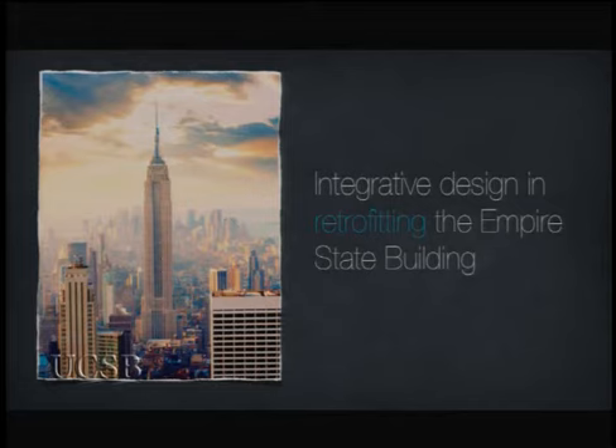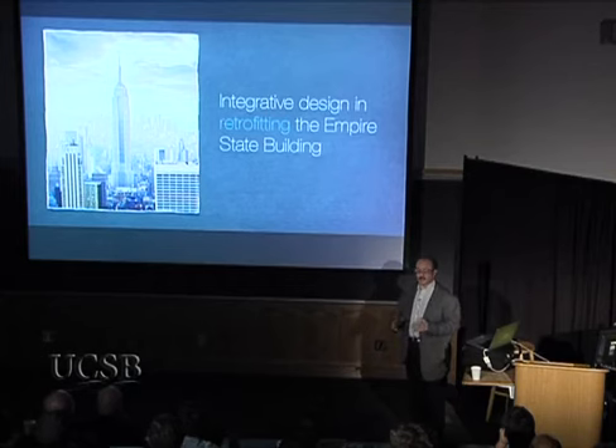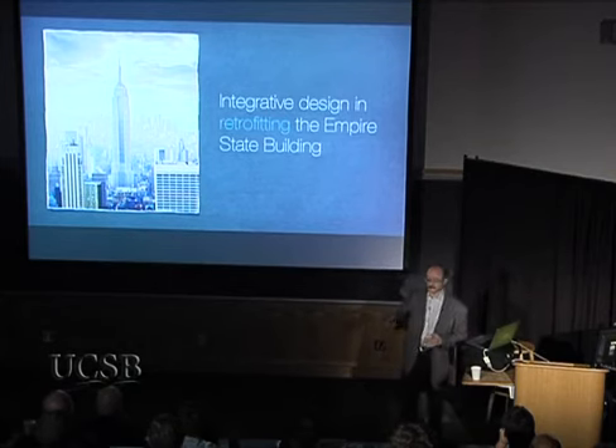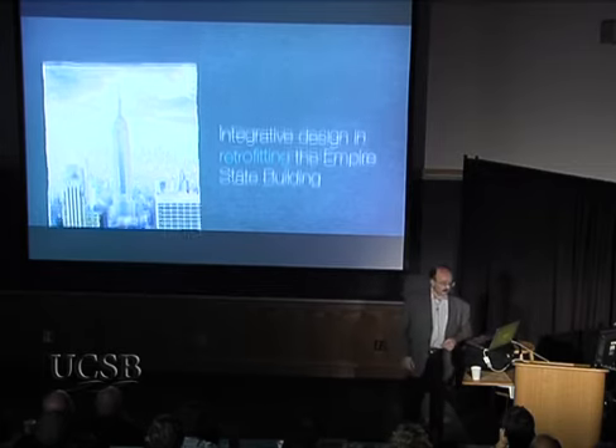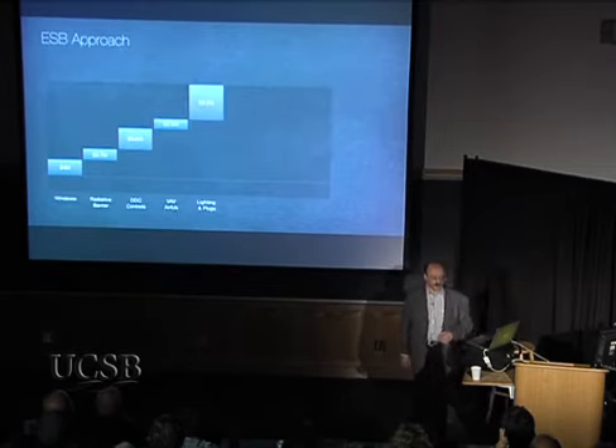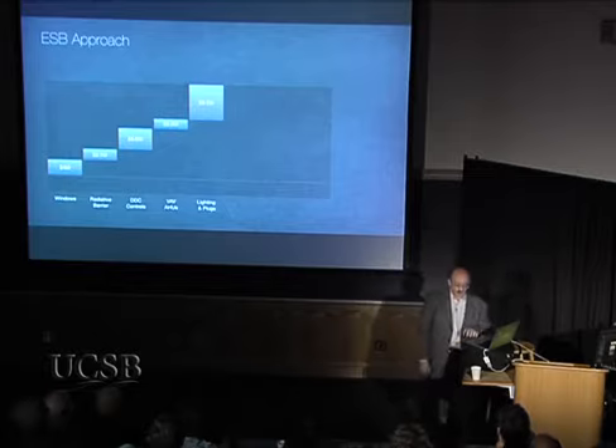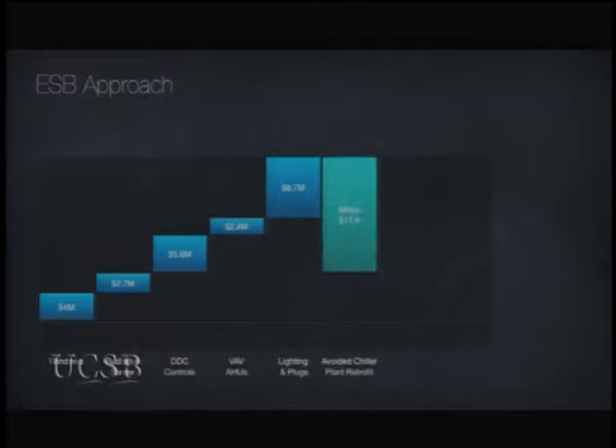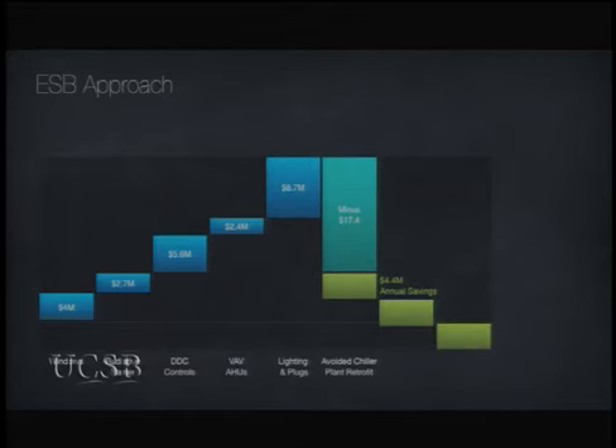Remanufacturing those 6,500 windows on site into super windows that pass light but block heat, plus better lights and office equipment and such, cut the maximum cooling load by 1/3. Renovating smaller chillers instead of adding bigger ones saved $17 million, which helped pay for the other improvements and cut the payback time to just 3 years.